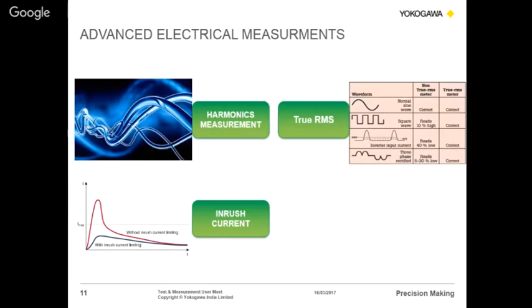In the same manner, at the basic level, we have equipment for harmonics measurement, true RMS measurements, inrush current measurements, and VFD measurements. Harmonics measurement is not easy, but it is a critical parameter in an AC system. Because when harmonic content is higher, losses are also higher. For inrush current, if you see motors, when you switch on the motor the starting current will be higher, that is called the inrush current, and that measurement is also a critical parameter.